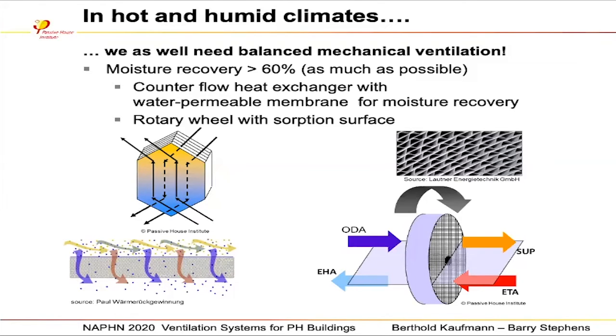ERV means you have, together with the heat recovery, the pure dry heat recovery, this heat exchanger can have humidity recovery, as we call it. And that means the membrane, if you use a membrane heat exchanger, the membrane allows for water diffusion from the humid side to the dry side. And that means you can make use of the latent heat of water.